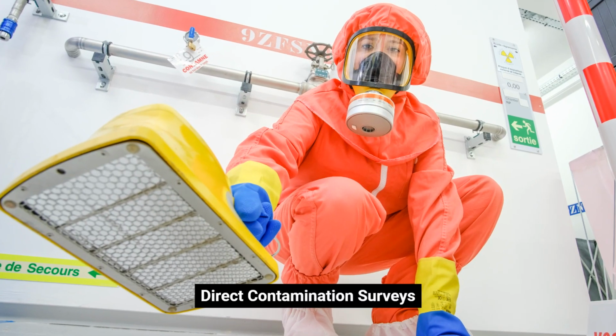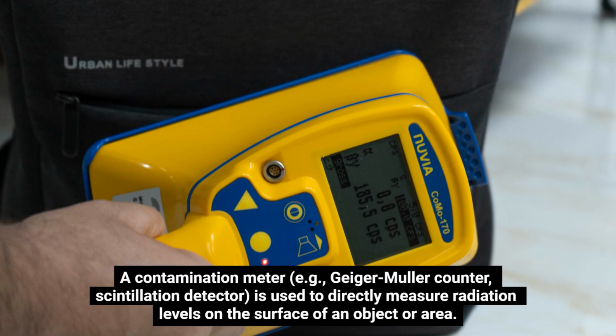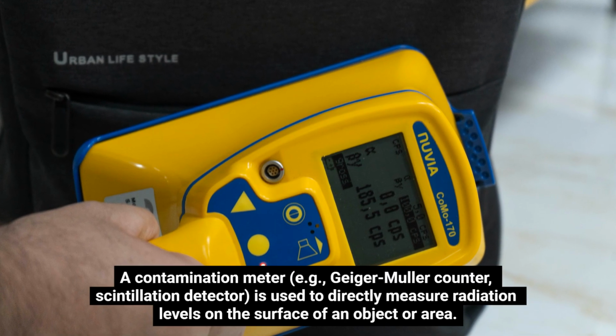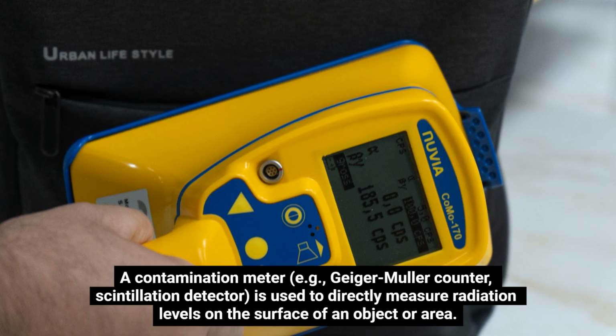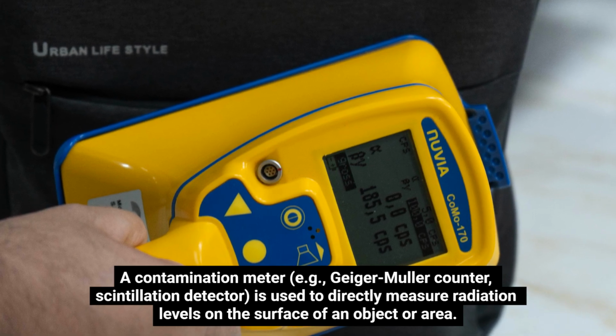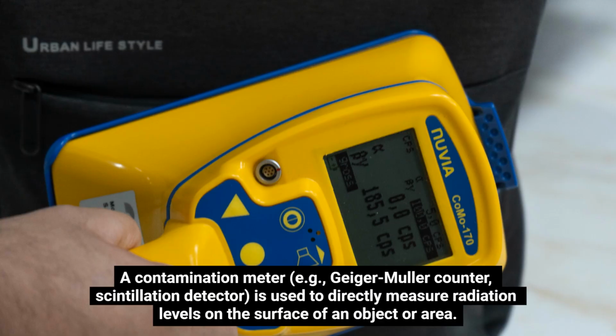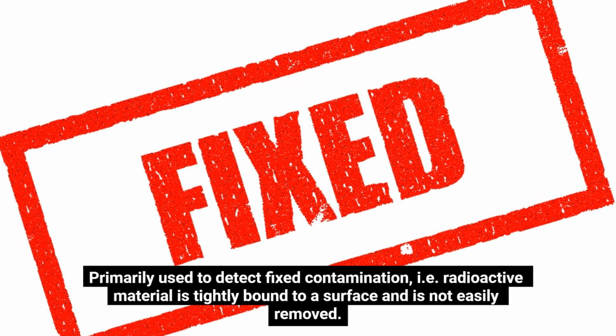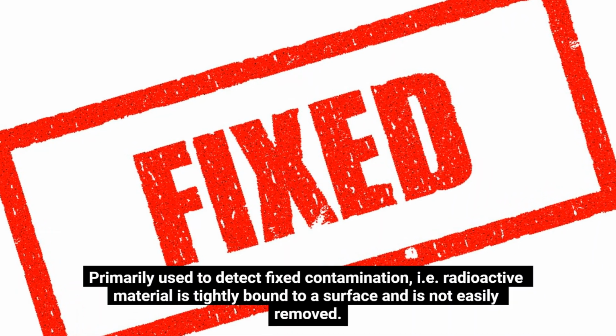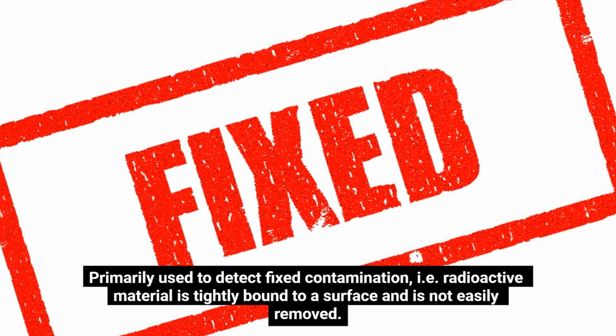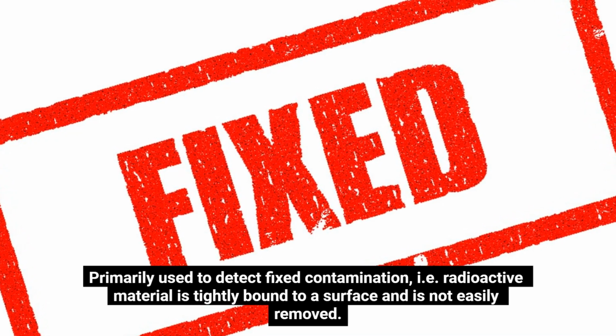Direct contamination surveys. A contamination meter, e.g., Geiger-Müller counter, scintillation detector, is used to directly measure radiation levels on the surface of an object or area. Primarily used to detect fixed contamination, i.e. radioactive material is tightly bound to a surface and is not easily removed.